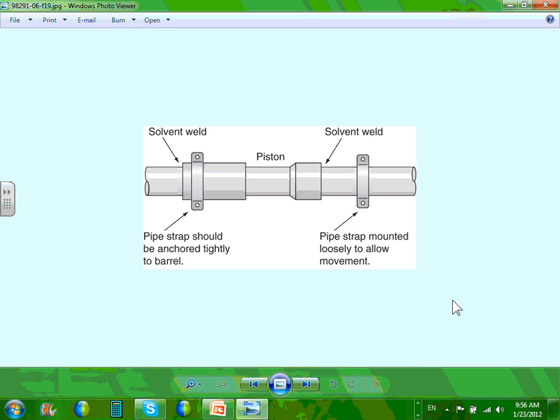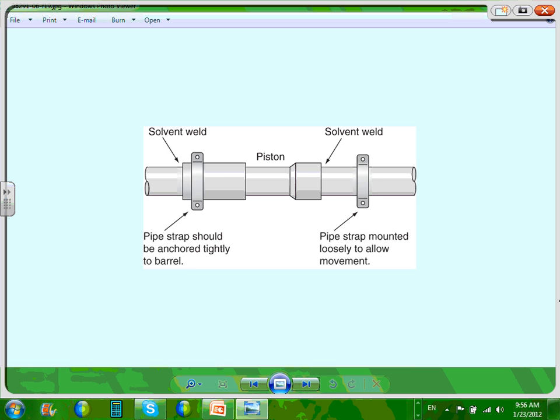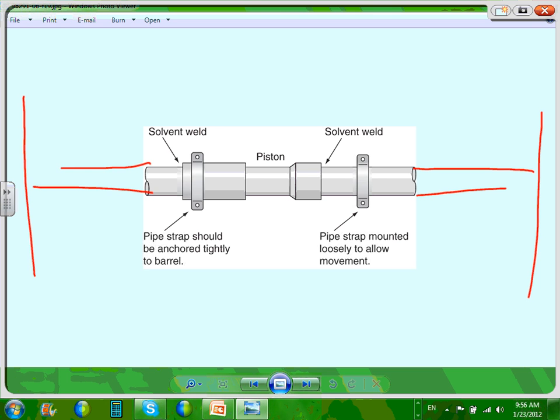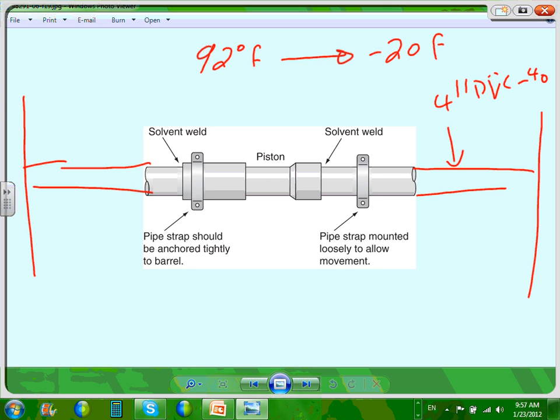And I'm hoping, if you're using PVC, especially PVC conduit, this applies to all other conduits too. If you're using PVC conduit, you have to pay attention to the expansion of the conduit. So take this: if I have a conduit going from this wall to this wall, this conduit here is 4-inch PVC schedule 40. Outside, exposed to the elements in Minnesota, the highest temperature for calculation, I think they used 92 degrees Fahrenheit. The lowest temperature, minus 20, I believe, minus 20 Fahrenheit. Again, these are for calculation purposes.